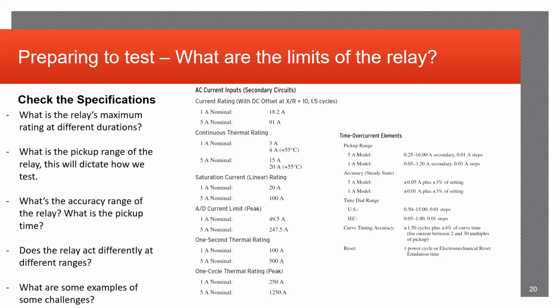A lot of this information seems like it would be redundant, especially after you test a bunch of relays, but especially nowadays where there are so many different types and versions and standards that clients may use, it's fairly important to identify that you not only have the correct relay manual, but you identify the limits of that relay specifically.